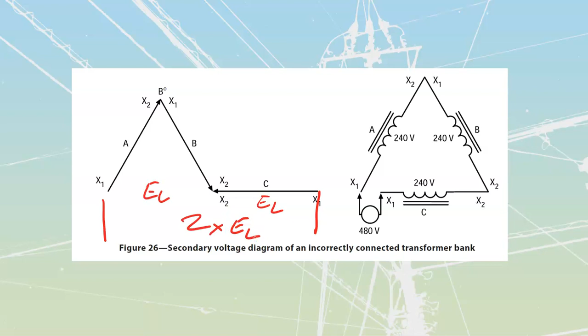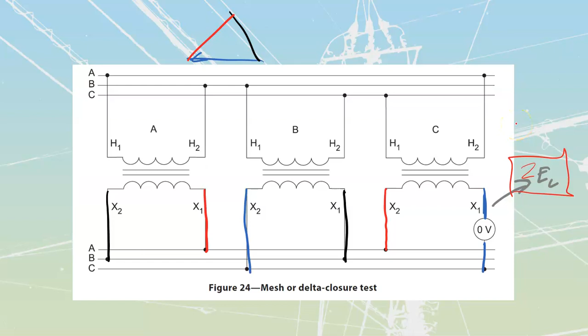Doing that closure test, you're always going to be looking for line voltage or less. It's going to be quite apparent, although the voltage value will be in between 0 and line voltage. As soon as we have a fault, it's going to be evident because it will become double line voltage.